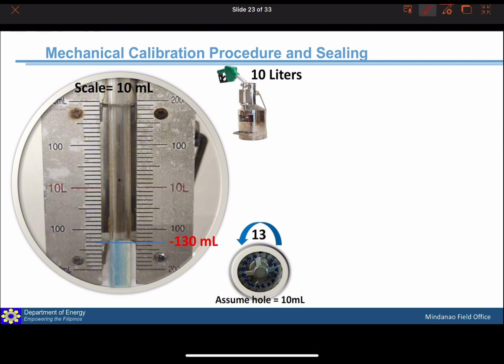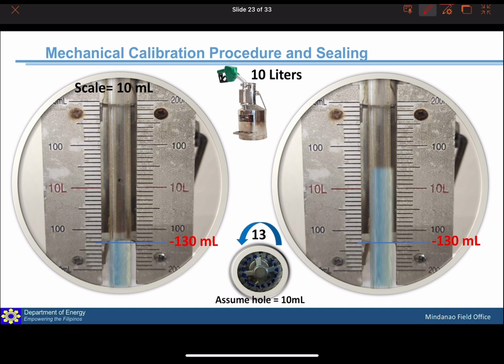After that, we will dispense again sa calibrating bucket and check the new reading. So, the new reading is plus 40 ml. So, this is the 0 or the baseline. And then, so, solving for the actual adjustment or actual value per hole is 170 divided by 13. So, ang value pala is 13 ml per hole.